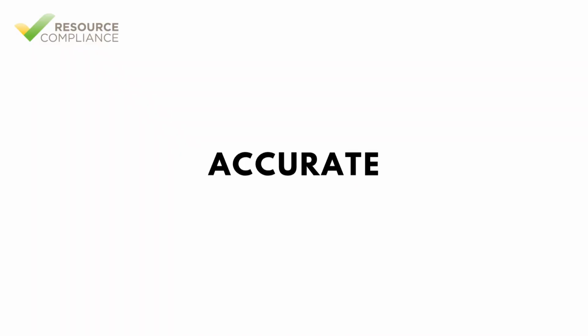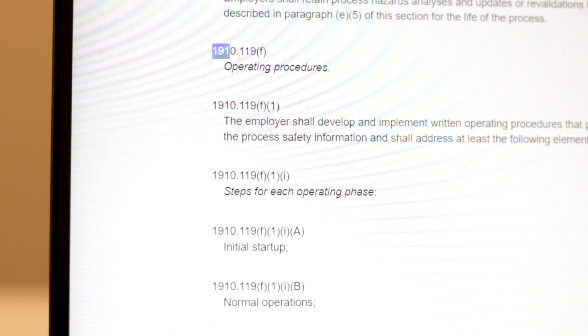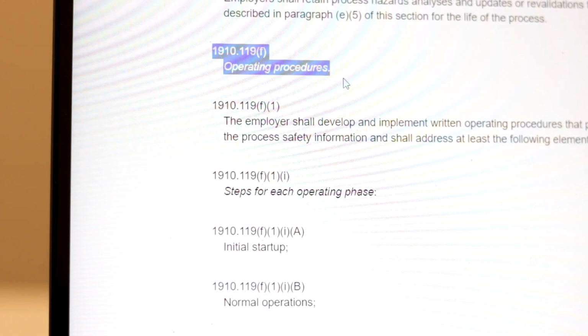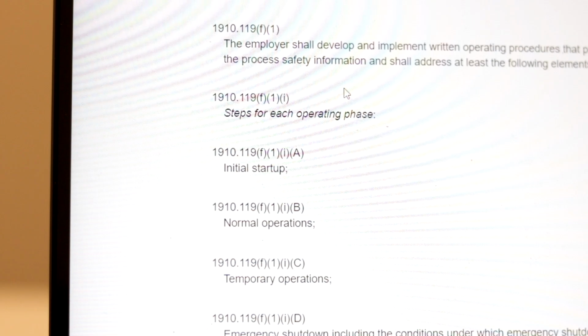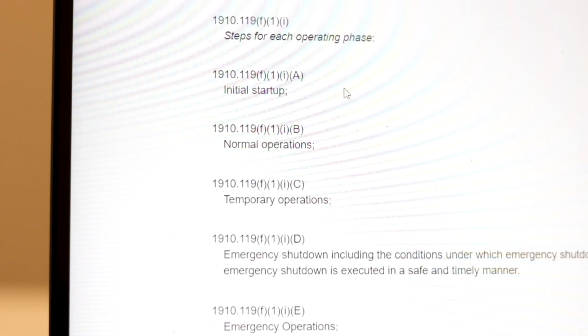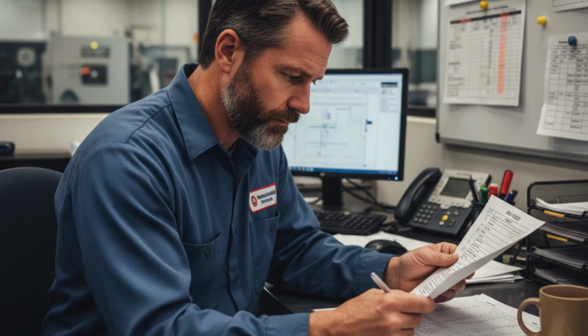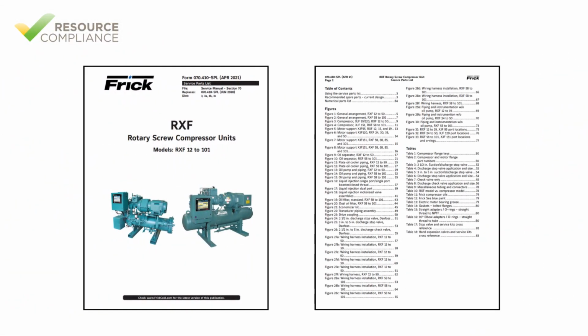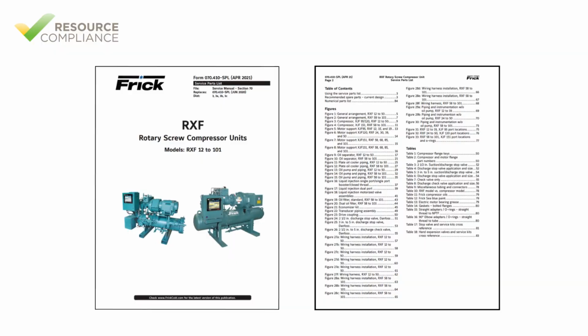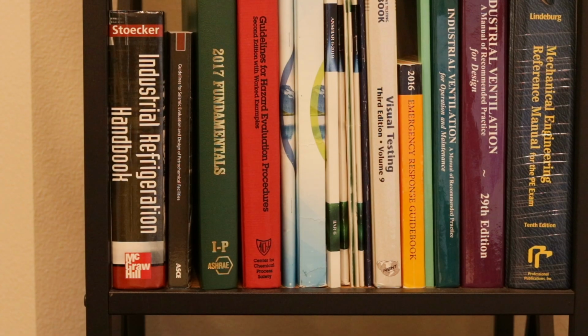It should go without saying, but SOPs must be accurate. RMP and PSM require that operating procedures be reviewed as often as necessary to assure that they reflect current operating practice. Additionally, if an ammonia refrigeration system has over 10,000 pounds, the SOPs must be certified annually to ensure they are current and accurate. There are many helpful resources for developing SOPs. Manufacturer literature is a great place to start. IIAR has excellent templates available in their published literature.